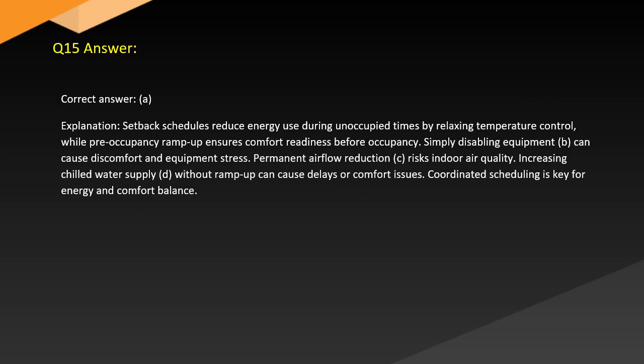Answer. Correct answer: A. Explanation. Setback schedules reduce energy use during unoccupied times by relaxing temperature control, while pre-occupancy ramp-up ensures comfort readiness before occupancy. Simply disabling equipment, B, can cause discomfort and equipment stress. Permanent airflow reduction, C, risks indoor air quality. Increasing chilled water supply temperature, D, without ramp-up can cause delays or comfort issues. Coordinated scheduling is key for energy and comfort balance.